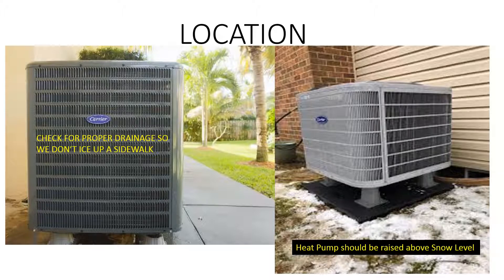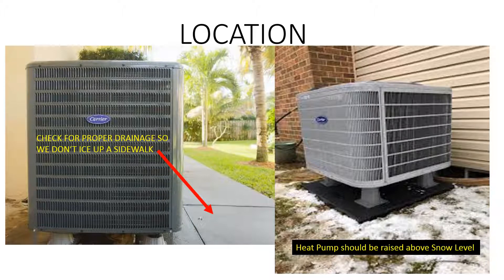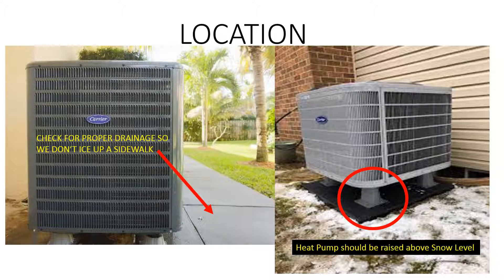One of the first things you need to do when installing a heat pump is to consider the location. You need to check for proper drainage so we don't ice up the sidewalk. When the outdoor coil defrosts, water will drain off the heat pump, and if it drains onto a nearby sidewalk it can cause a hazardous situation. Also, a heat pump should be raised above the snow level so that snow will not hamper the defrost of the coil.